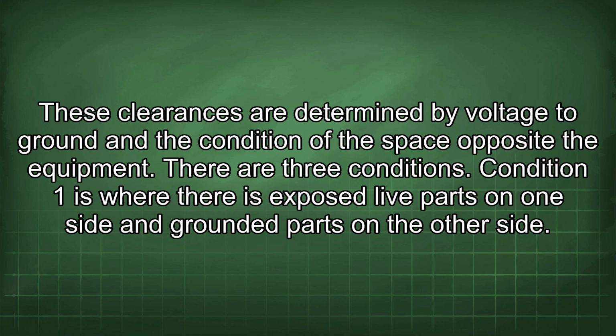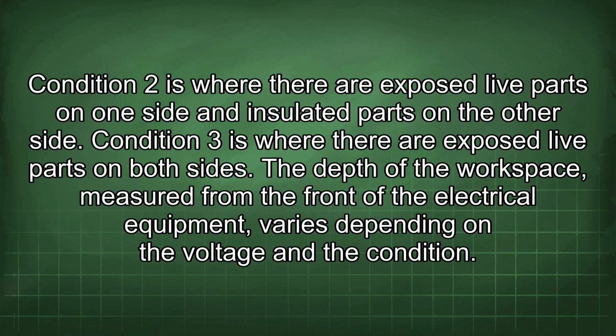There are three conditions. Condition 1 is where there are exposed live parts on one side and grounded parts on the other side. Condition 2 is where there are exposed live parts on one side and insulated parts on the other side. Condition 3 is where there are exposed live parts on both sides.